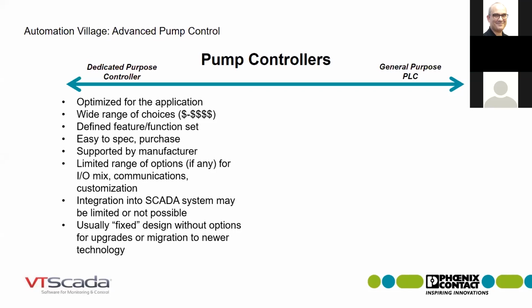The downside of a dedicated purpose controller is that you generally have a very limited range of options, if any, for the type of mix, the inputs and outputs available, your communications capability, and the desire to customize it in some particular way. As a result of those limitations on communications and connectivity options, it may be difficult or impossible to integrate into your SCADA system. Usually it's a fixed design, meaning you don't have options for upgrading—you buy it, put it in, it works for however many years. But when it reaches end of life, you're stuck with rip and replace, with probably no opportunity for migration into newer technology. So that's a quick look at the attributes of a dedicated purpose controller.